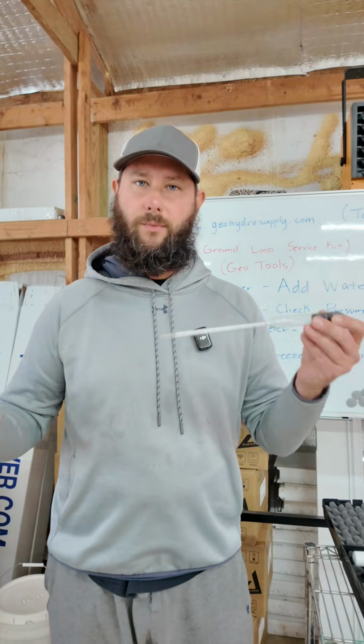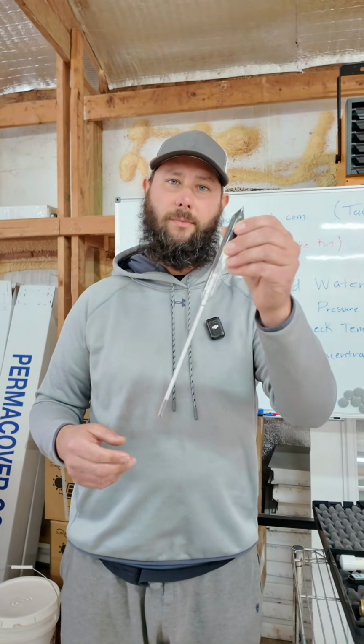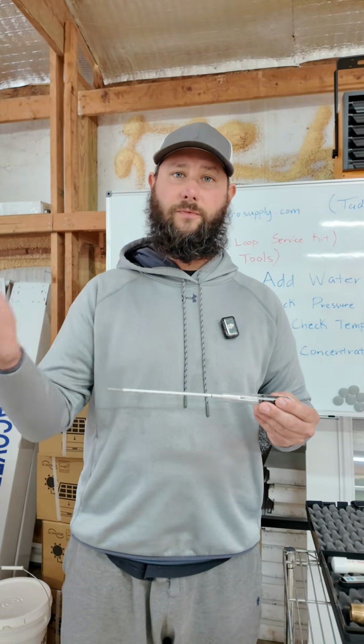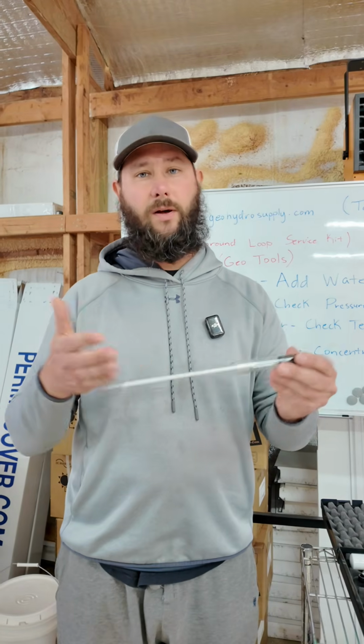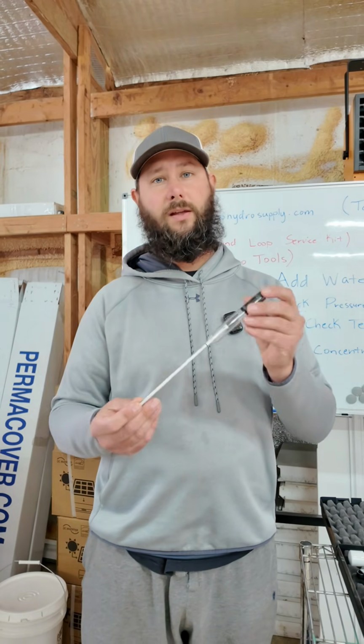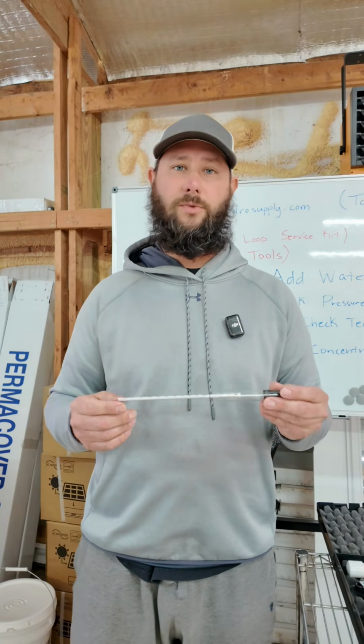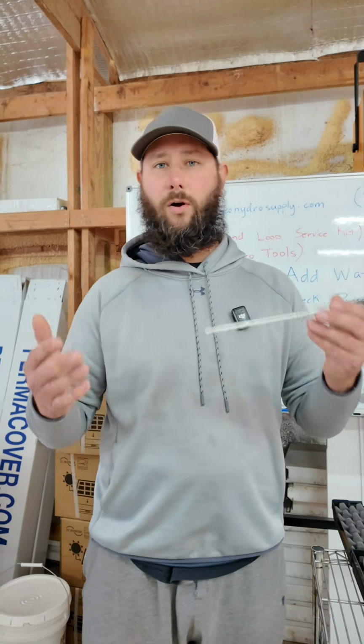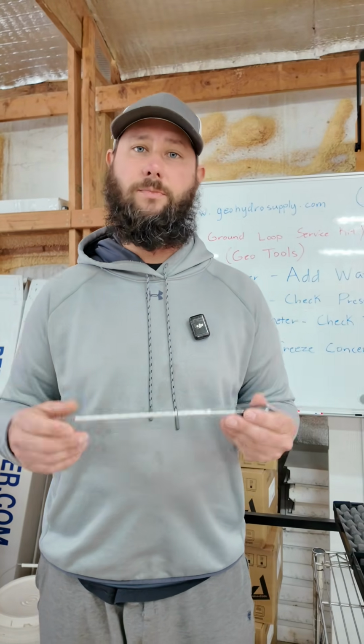What does each tool do and why does it matter? This is the hydrometer. This is for taking the loop fluid, measuring it, and seeing what the specific gravity is of that fluid. Then we can tell how much antifreeze we have in our closed loop geothermal system. We have to have the right amount of concentration. If we have too much antifreeze, it can cause poor performance or poor heat transfer. If we don't have enough antifreeze, it can cause our loop to freeze.